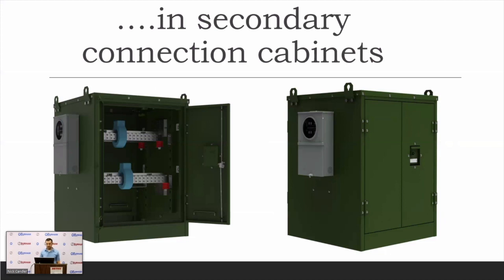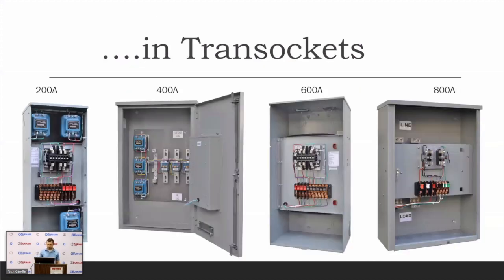So, Nick, I'm assuming those transockets are mostly meant for saving space at the customer site. It is, yeah, good question. Space is an issue, but we see a lot of utilities are doing this for convenience. Obviously, in the industry, the last 5 to 8 years, we've lost a lot of what we call legacy linemen, folks who had that tribal knowledge to build all this stuff out. And it's much more convenient if they've outsourced the installation of this stuff to the customer for a contractor to swing by the utility, grab one of these off the shelf, then the utility will come out and install the meter later or energize it. So there's some convenience factors there.